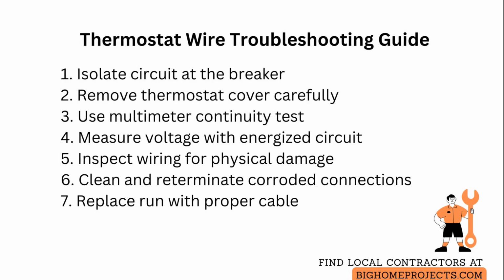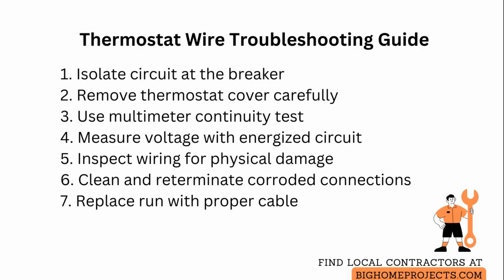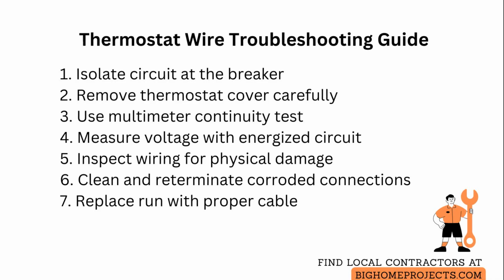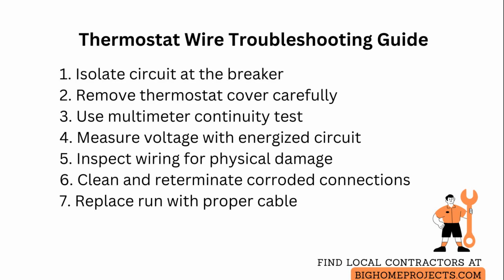If the meter shows very low resistance but the thermostat still reads no voltage at the load terminal, switch the meter to the voltage setting and energize the circuit briefly to measure between the transformer's hot output and the corresponding thermostat terminal while observing safety precautions.